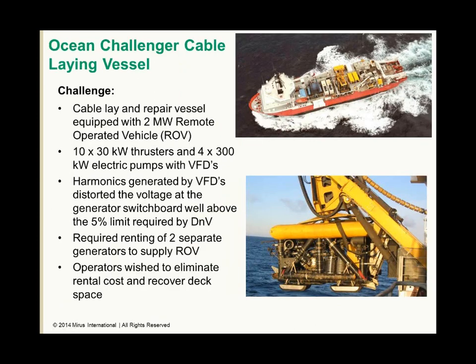The cable-laying vessel used a remote-operated vehicle, or an ROV, as shown here, to dig the trench and lay the cables. This ROV was equipped with 10 30-kilowatt thrusters and 4 300-kilowatt electric pumps. They were all equipped with VFDs. Harmonics they generated distorted the voltage well above the 5% limit required by the certifying body, DNV, when supplied from the vessel's main generator. Therefore, 2 separate generators were required to feed the port and starboard sides of the ROVs separately.